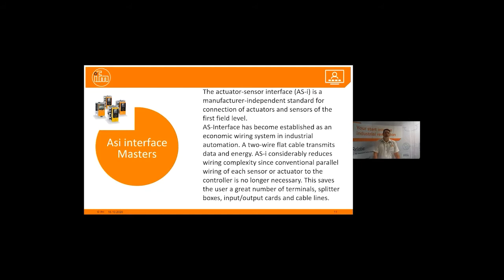ASI interface, actuator sensor interface, that's what ASI stands for. It's a manufacturer-independent standard for connection of actuators and sensors of the first field level. ASI interface has become established as an economic wiring system in industrial automation. A two-wire flat cable transmits data and energy. ASI considerably reduces wiring complexity since conventional parallel wiring of each sensor or actuator to the controller is no longer necessary. This saves the user a great number of terminals, splitter boxes, input/output cards, cable lines, points of failure. I can continue with this list.